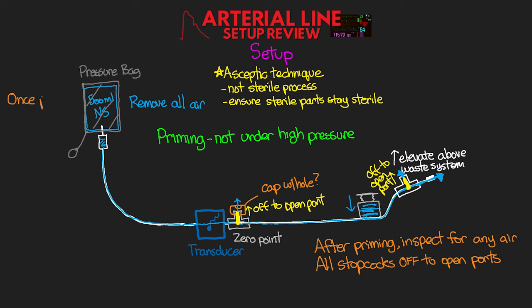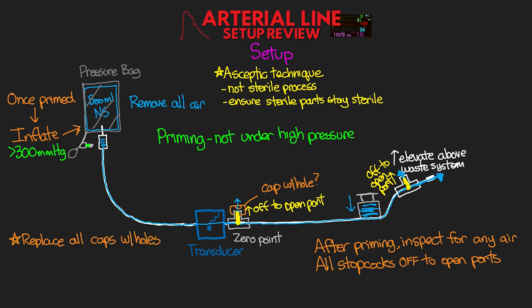Now, once you have the entire system fully primed, go ahead and inflate the pressure bag. We need to ensure that we have greater than 300 millimeters of mercury of pressure inside of the bag. There should be a gauge that will show the level of pressure, and typically we'll have a green section once the proper pressure is achieved. There's also a waste gate on the pressure bag that should prevent any overinflation. Once that is fully inflated, go ahead and replace any temporary caps with holes over those open end ports on the three-way stopcocks. These are only used for priming and need to be replaced with actual caps that do not allow flow.